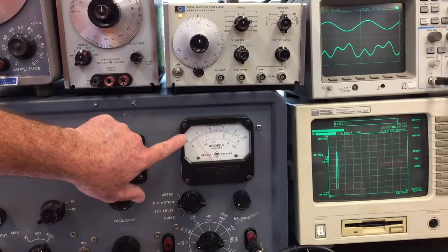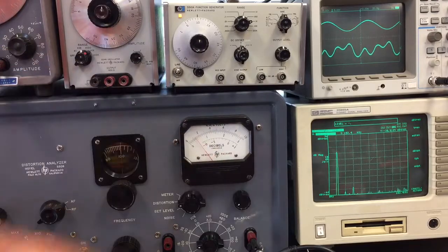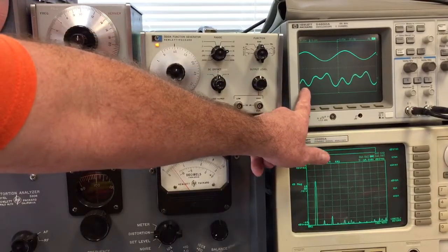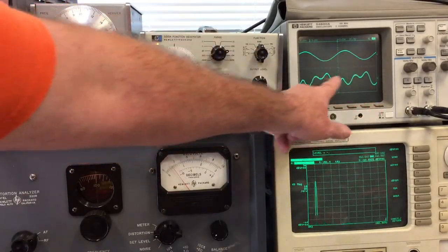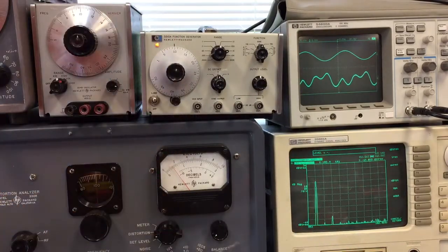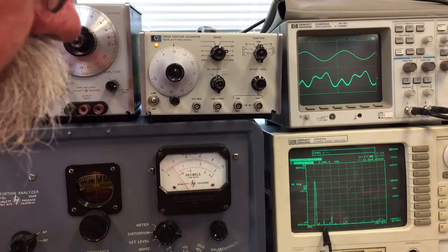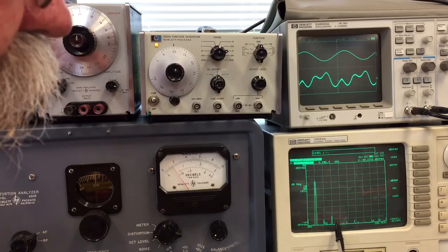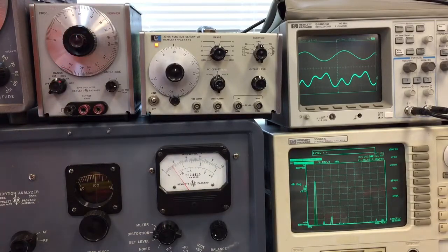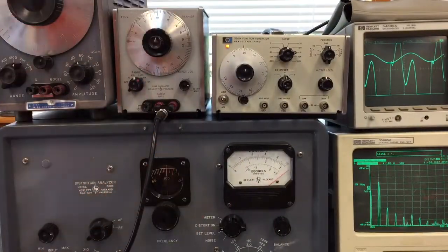On the 1% scale it's reading a little over 0.1%, about 0.15%. You can see there's a real strong third harmonic — 1, 2, 3 — compared to the incoming wave. Here's the fundamental; each division is 10 kilohertz, so the fundamental is at 10 kHz. The second harmonic at 20 kHz is pretty small, but the third harmonic is much stronger. There's some more content in the noise but they're pretty small.